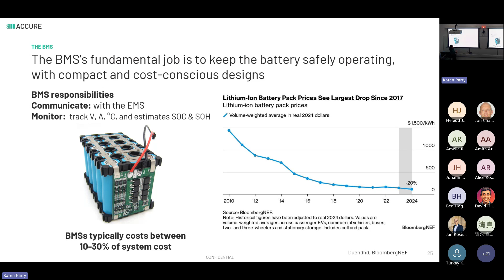Again, the main responsibility of the BMS is to keep the system safe, versus accurately calculate the state of charge. So what we often see are large error margins. For LFP batteries, which are the main ones for energy storage, it's very common to see an error range of 5 to 15% in the calculation of state of charge, because of that small computational power from the BMS.